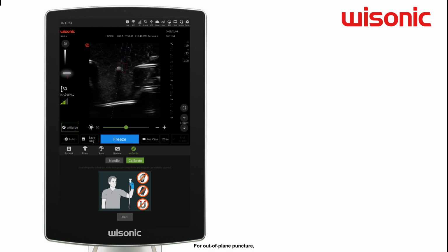For out-of-plane puncture, adjust the target box location by changing the angle and degree of the needle. Advance the needle to reach the target. The dotted line on the screen indicates the needle trajectory. The green target box indicates the needle tip is at the same plane of the ultrasound beam.